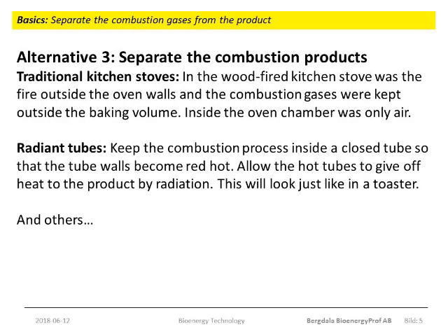The third main option is to heat up the process chamber walls from the outside and then rely upon radiative heat transfer from the walls to the product. This is the common situation with electrical heating. The heating elements in an electric furnace are usually situated in or just inside the process chamber walls and heat the product only by radiation, just like in a bread toaster. And this can also be achieved using radiative tubes.